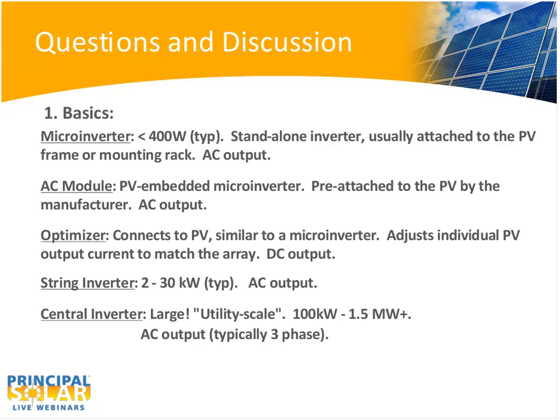There are two kinds of optimizers in use today. One just simply goes straight across, meaning if you feed it with, let's say, 30 to 40 volts DC input at 8 amps, it will strive to come out with approximately whatever current is present in the remainder of the array and adjust its output voltage to match that current. I know this is a little bit technical, but it becomes more of what's called a constant current device.